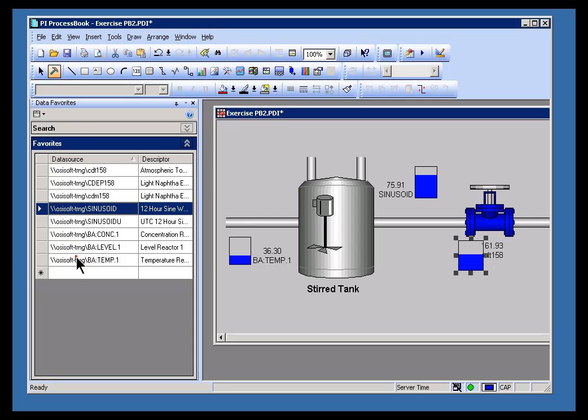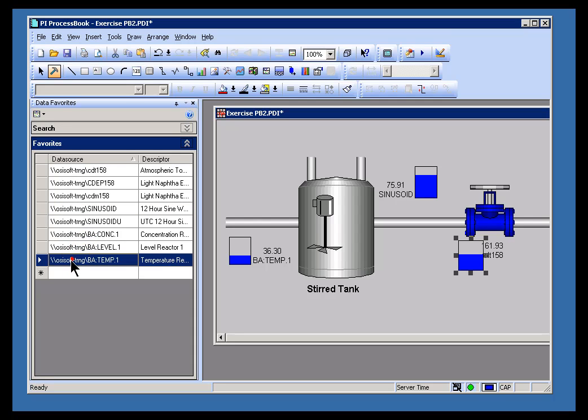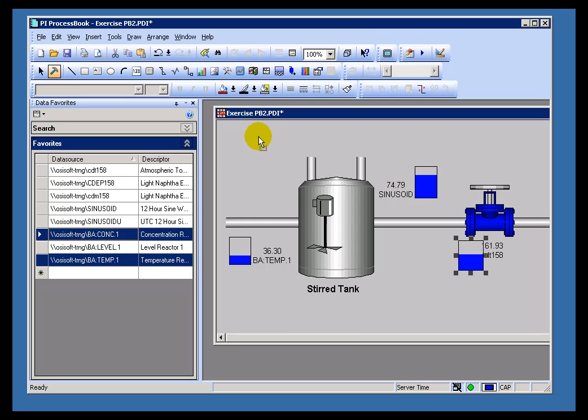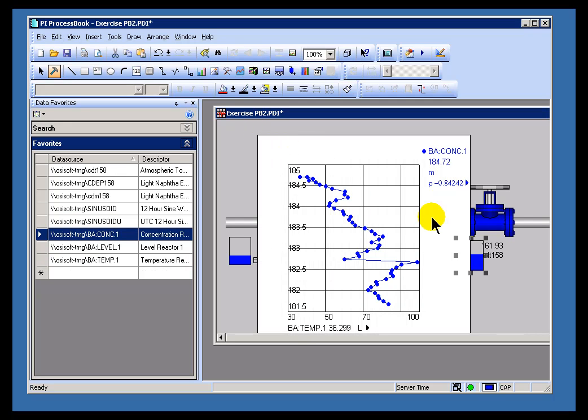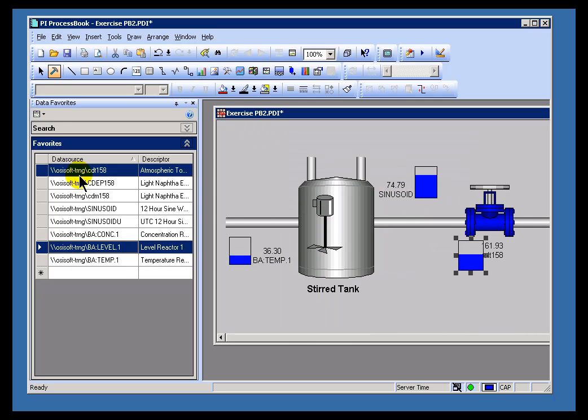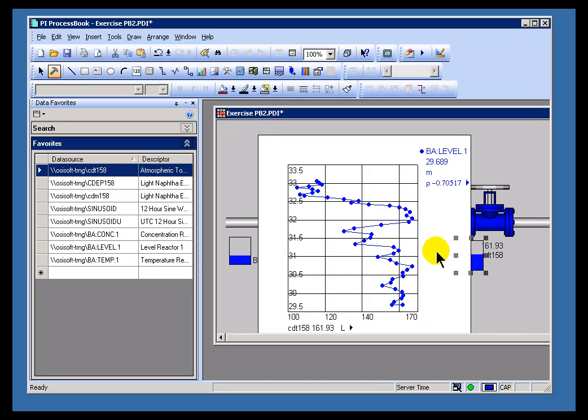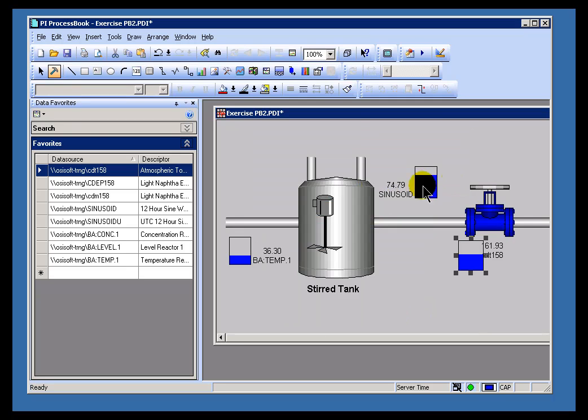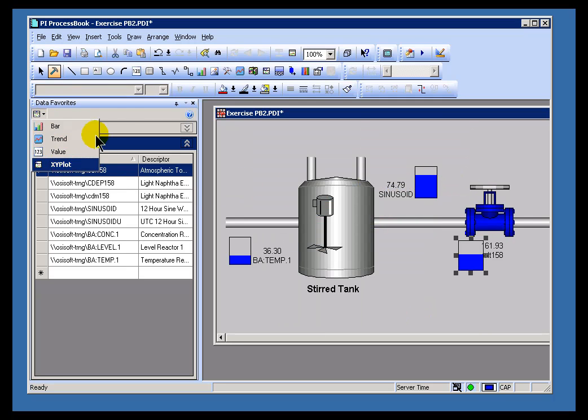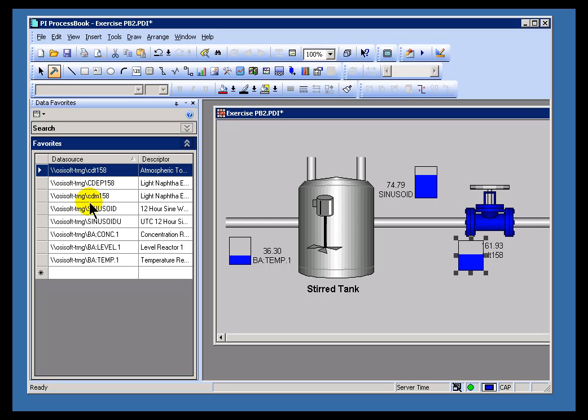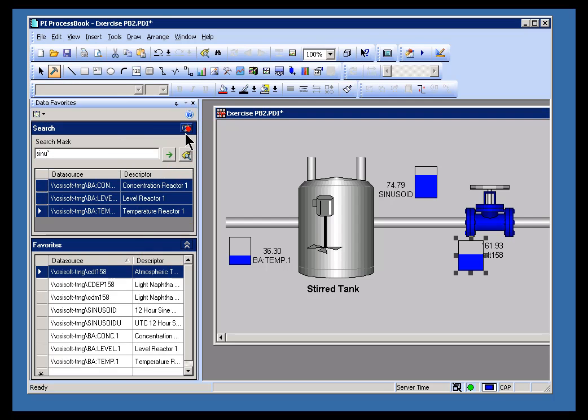The point is you can do this to any of these things. Let's compare concentration to temperature. Drag this over. It's a fairly strong inverse correlation. Yeah, that one's strongly correlated as well. Well, in any case, the whole idea now is you've got this wonderful little engine. You can look at all your different favorites, and whatever else you can search for and just immediately drop XY plots to show you if there are any correlations between those process values that you may not be aware of already.